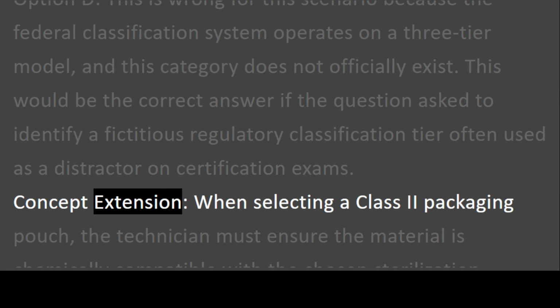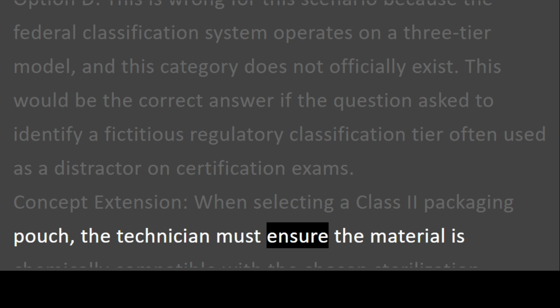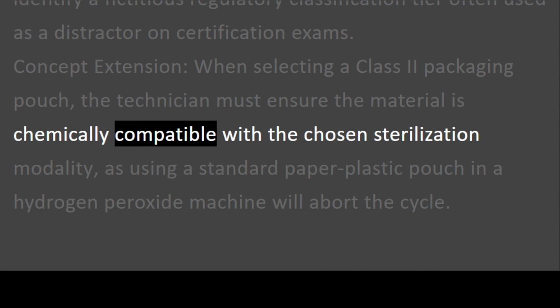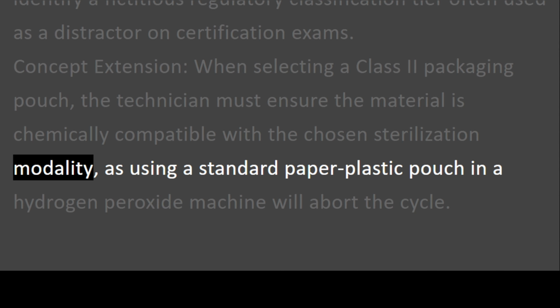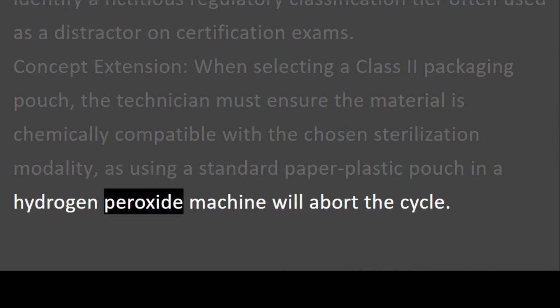Concept extension. When selecting a Class 2 packaging pouch, the technician must ensure the material is chemically compatible with the chosen sterilization modality, as using a standard paper plastic pouch in a hydrogen peroxide machine will abort the cycle.